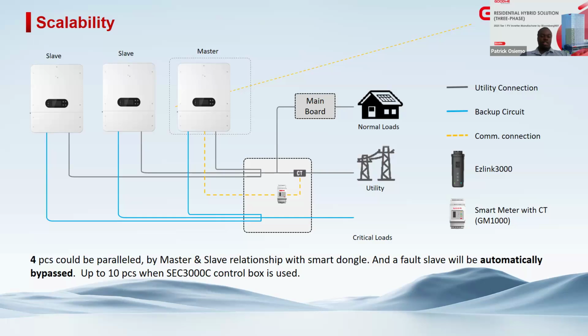Now, with the scaling up, you can see that we have shared loads. Whether you have 10 inverters, 1 to 10 inverters, the loads are shared on both the on-grid port and the backup port. So there's no need of separating your loads just so you can do independent powering from the various different inverters. All the inverters will be sharing the loads, whether they are connected to the grid or they're working off-grid.